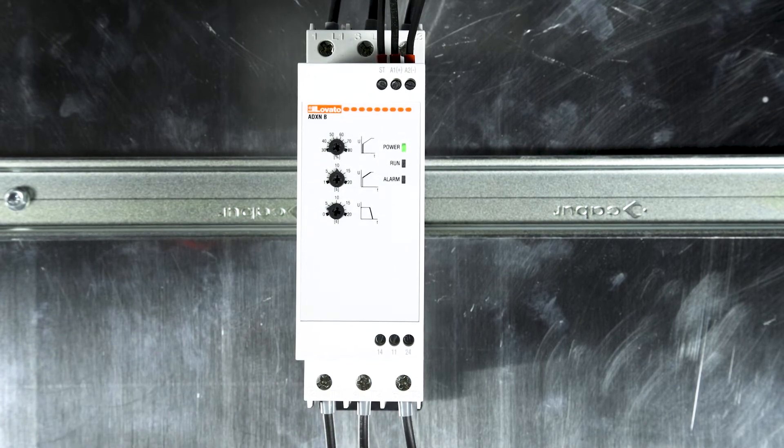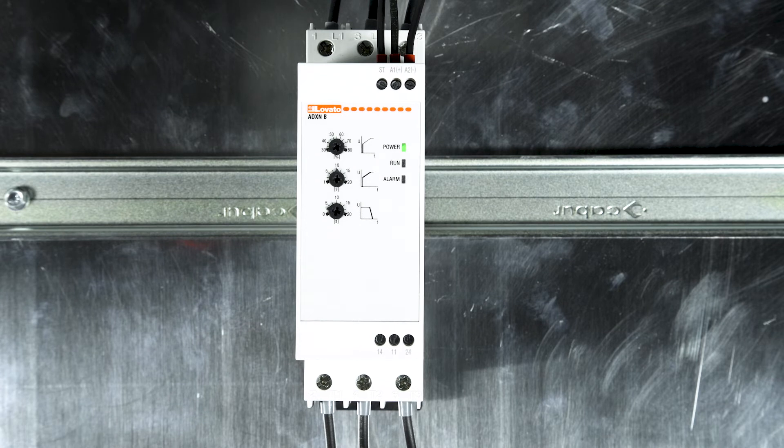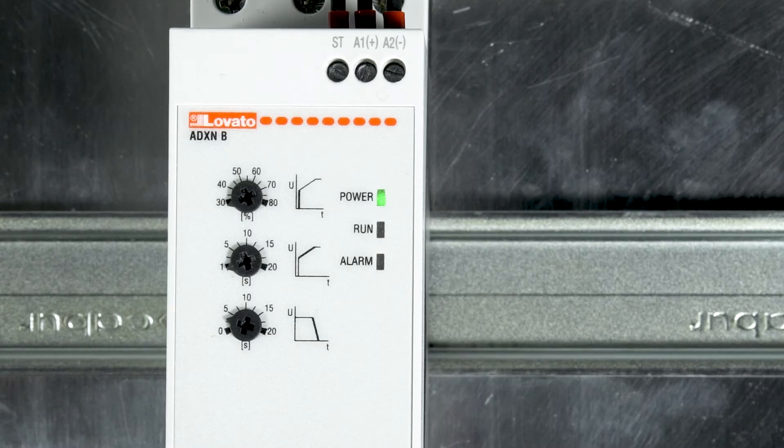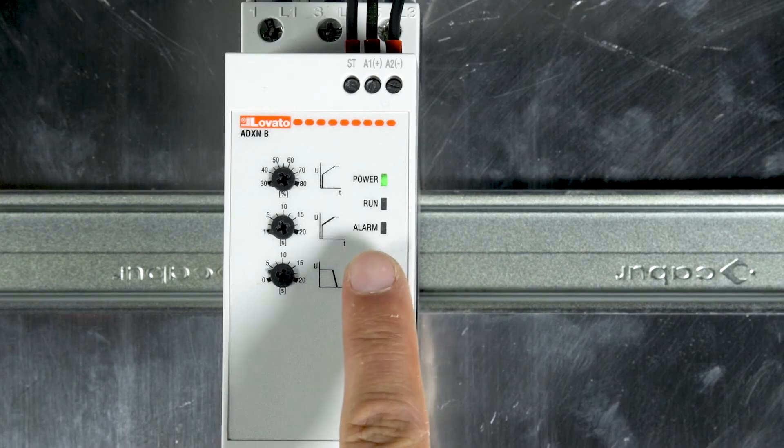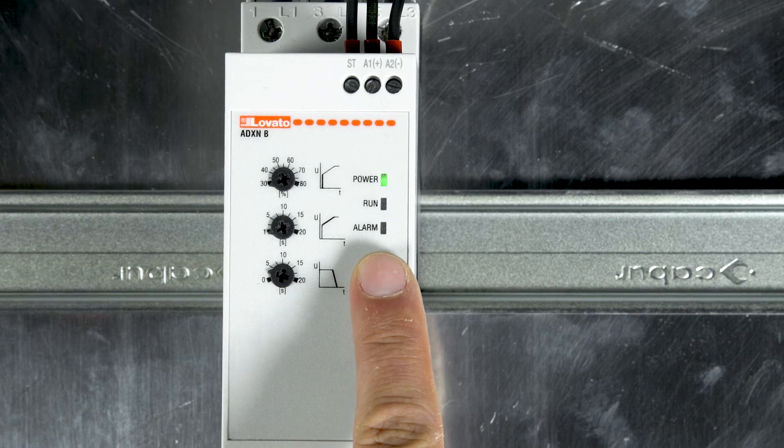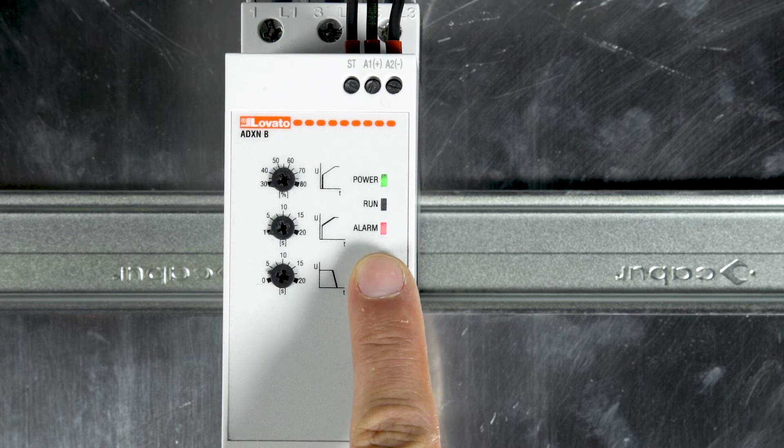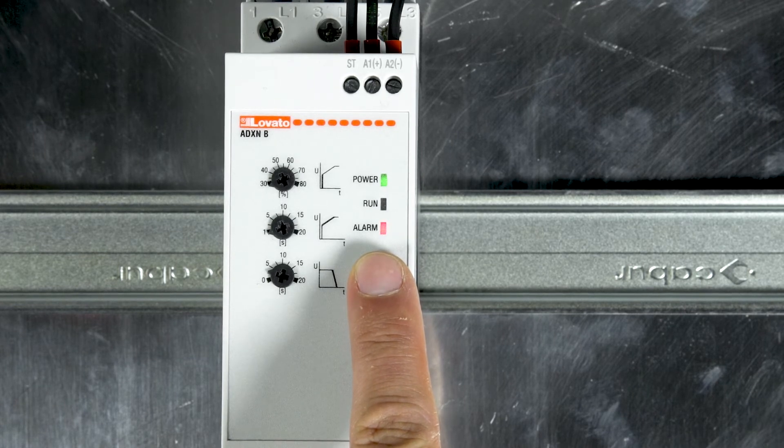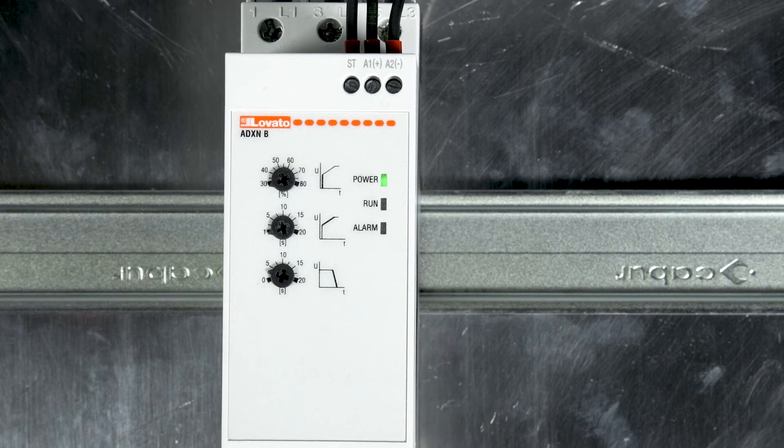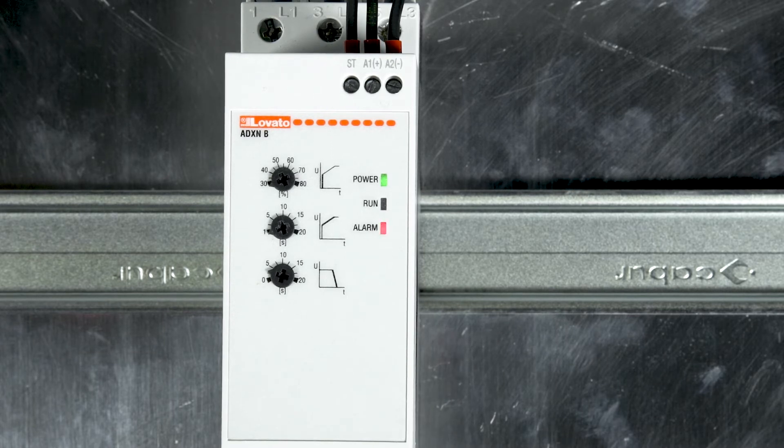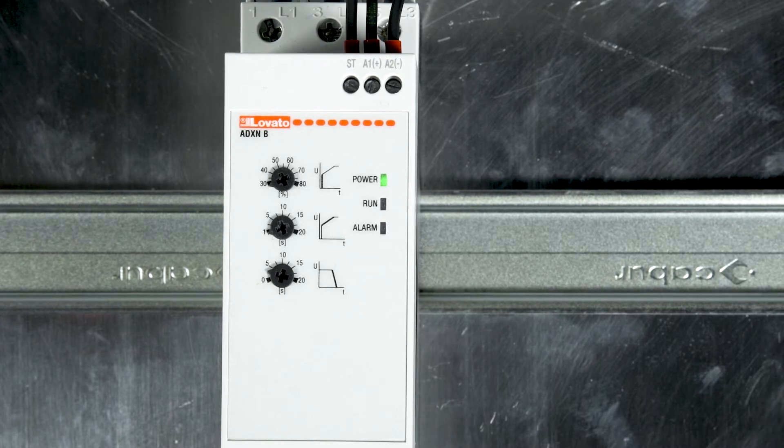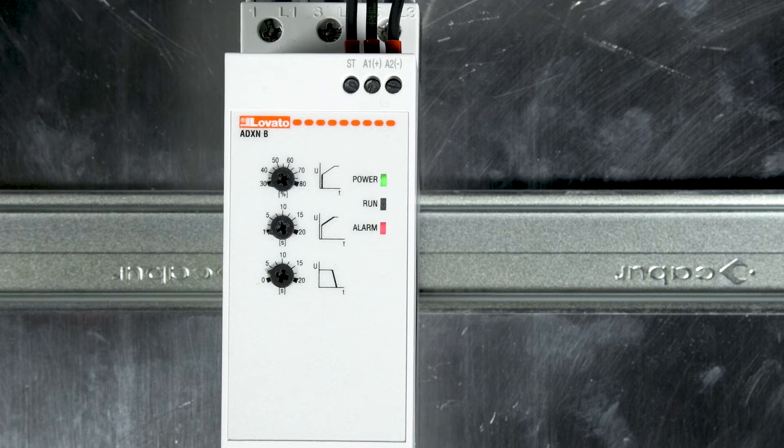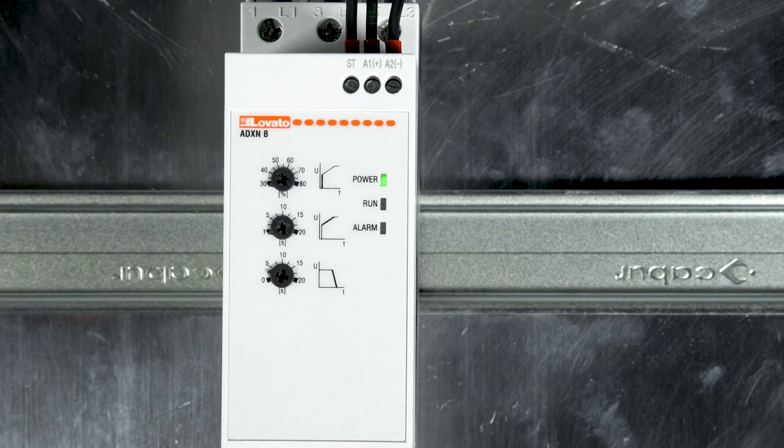From now on, if the soft starter input phases are not connected in the correct sequence L1, L2, L3, the red alarm LED flashes three times to signal the alarm A03 wrong phase sequence, as in this example. If you try to close the start contact, the soft starter protects the motor preventing its starting.